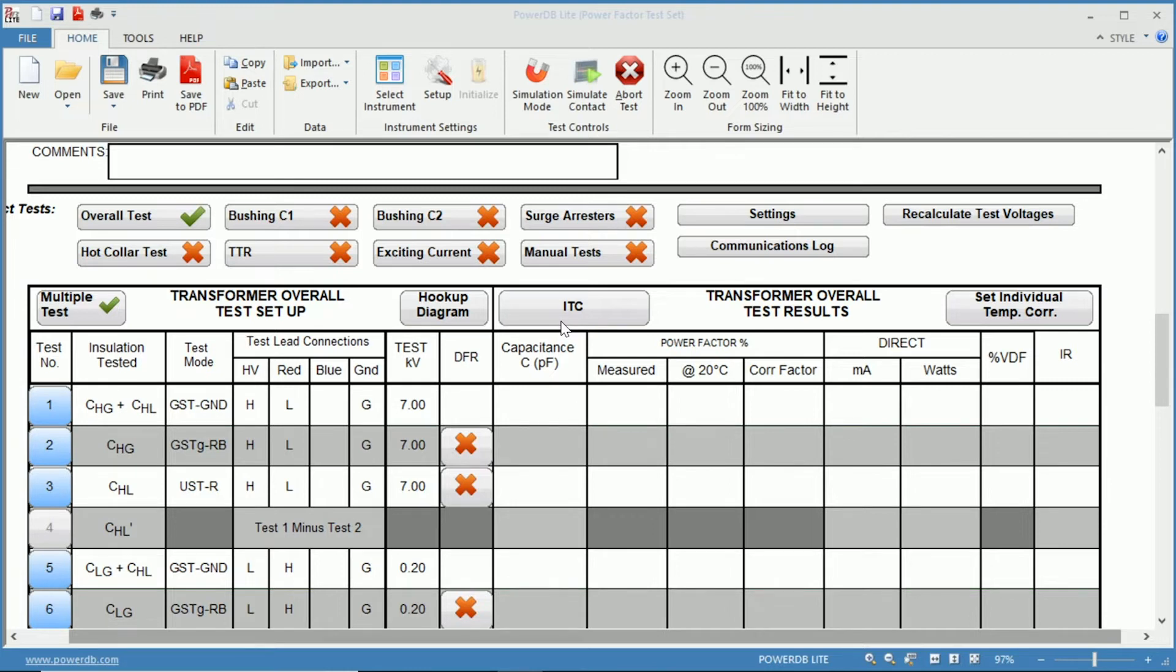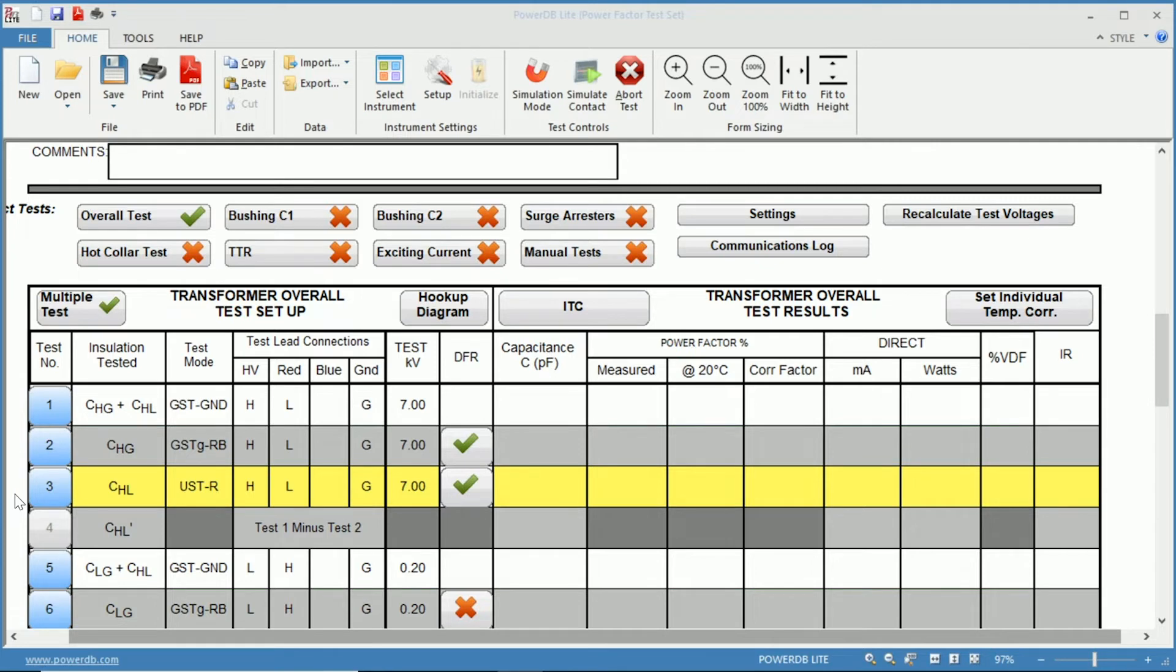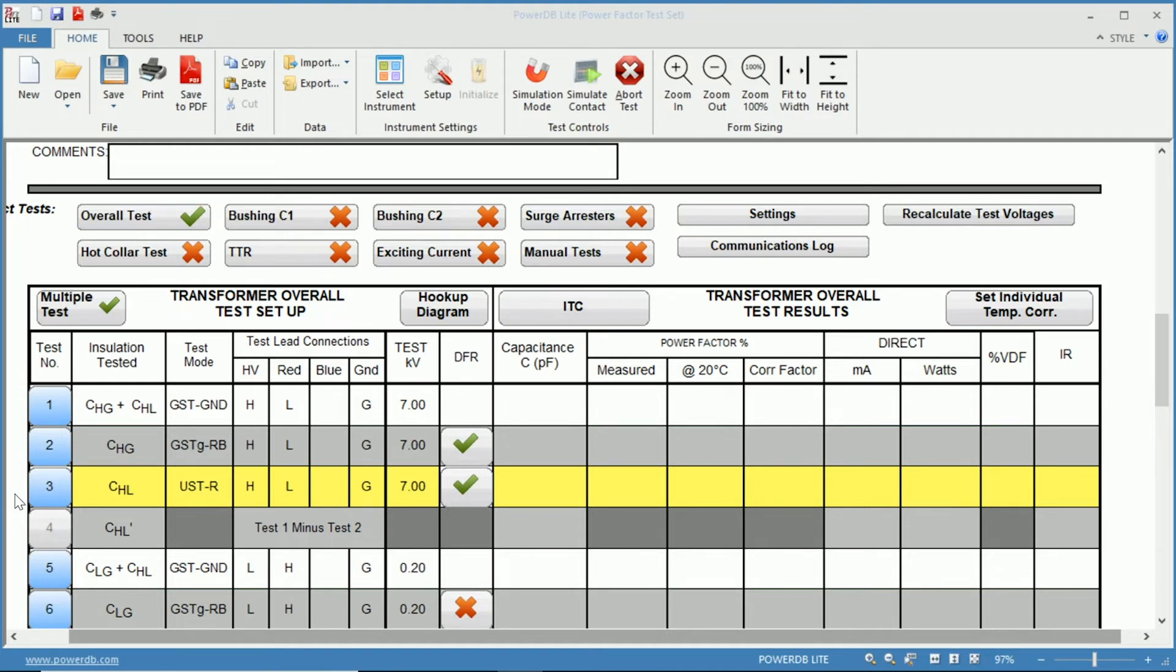And that's based off of what is called the DFR or the narrowband DFR which is a dielectric frequency response, which is essentially power factor performed at multiple frequencies. For a narrowband DFR that's between 500 and 1 millihertz, and this is particularly beneficial because power factor is much more sensitive at low frequencies. And with this frequency sweep of power factor you can now set an individual temperature correction factor for that very transformer and for that transformer only rather than using a table that just generalizes the correction factor.